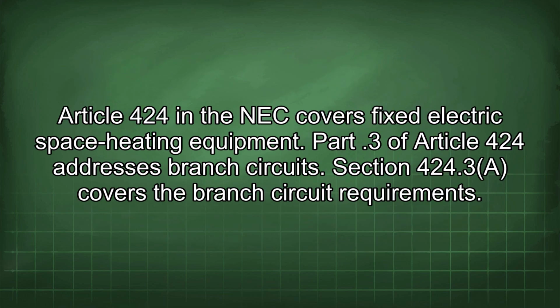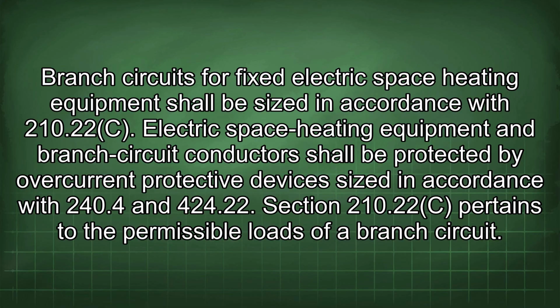Article 424 in the NEC covers fixed electric space heating equipment. Part 3 of Article 424 addresses branch circuits. Section 424.3 covers the branch circuit requirements. Branch circuits for fixed electric space heating equipment shall be sized in accordance with 210.22(C). Electric space heating equipment and branch circuit conductors shall be protected by overcurrent protective devices sized in accordance with 240.4 and 424.22.